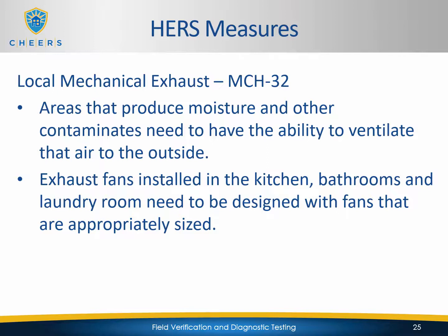Along with providing fresh air to the whole home itself, we want to make sure that we can take those source contaminants and get them directly to the outside, so that they're not just going to spill off into the regular house and then have the whole house ventilation system have to deal with them. If we can deal with them directly at the source, then that's going to improve the overall indoor air quality for the entire home. So these are going to be your kitchens, your bathrooms, your laundry rooms, where you're producing moisture, which is the main thing we're trying to get out. But in the kitchen, you're also going to possibly have oils and smoke and things of that nature that we want vented to the outside.